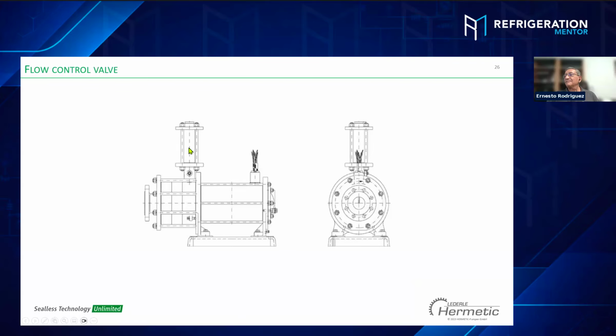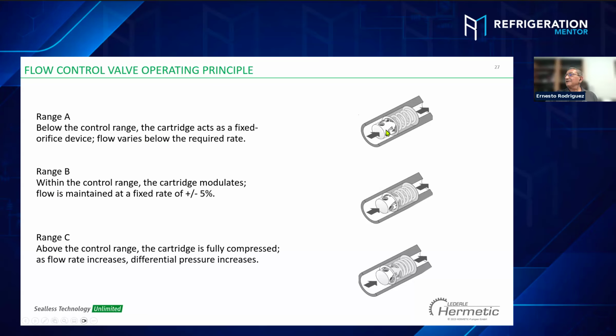Now we have the flow regulator. The flow regulator is a device installed in the pump discharge. Basically, it's a control valve with a V port and with a spring. Basically, when the system is demanding too much fluid, the port is going to be open. But at some point, you have multiple coils, multiple evaporators, and at some point the system is demanding too much liquid. The problem when you have too much liquid is that you have unbalanced pressure on the coils. It means in coil number one you have higher pressure versus coil number three, and you have a lack of liquid in multiple evaporators.